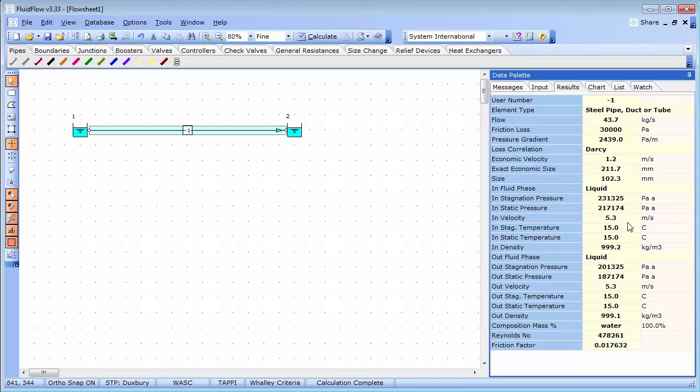A quick look at the suggested economic pipe size reveals that we should perhaps consider a size or internal diameter of around 211 millimeters. And this would equate to a flowing velocity of around 1.2 meters per second. This information is provided for the engineer to make a judgment call on whether or not he wishes to change the selected size of pipe in the system.